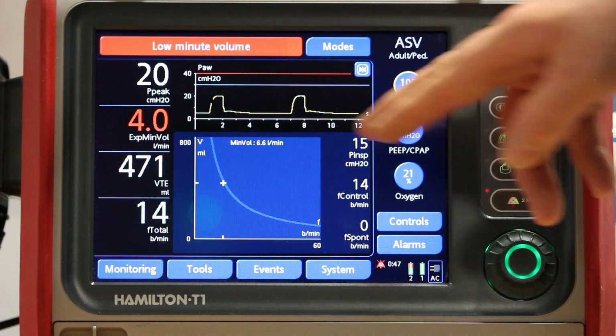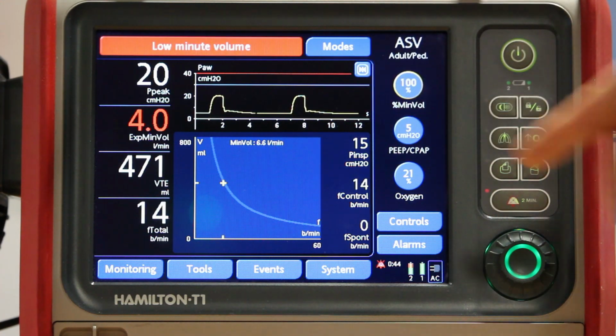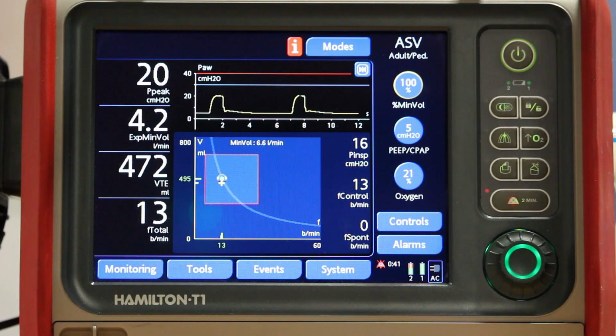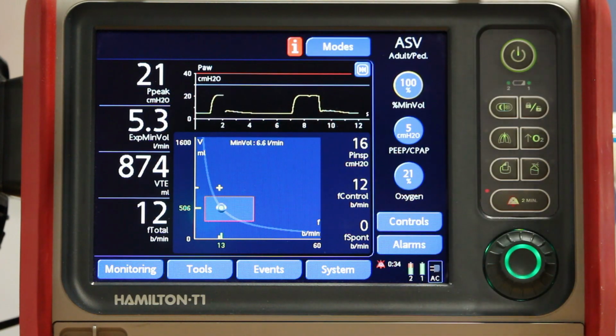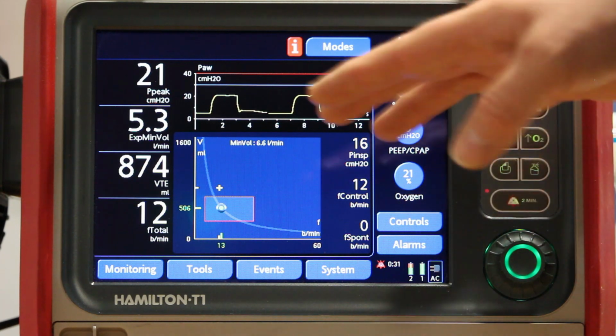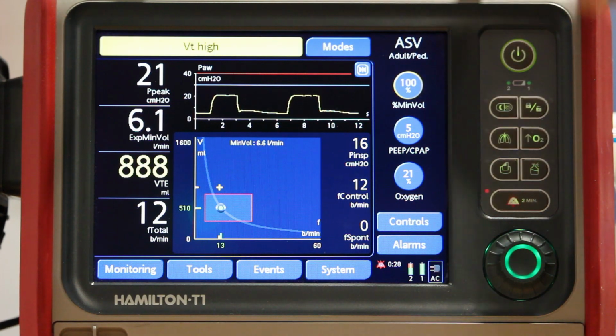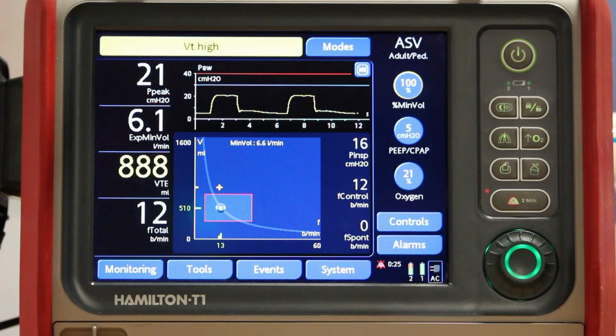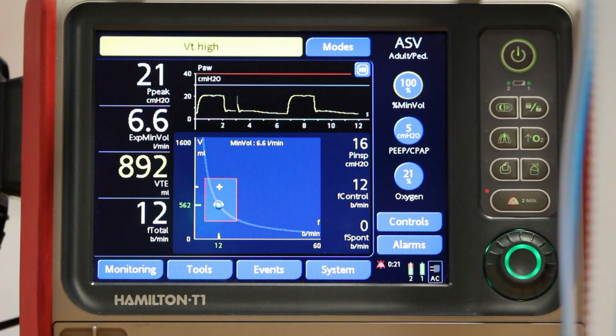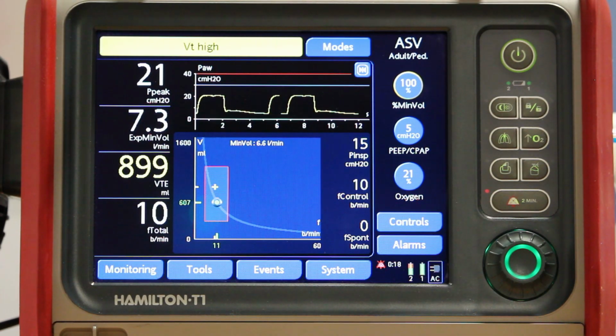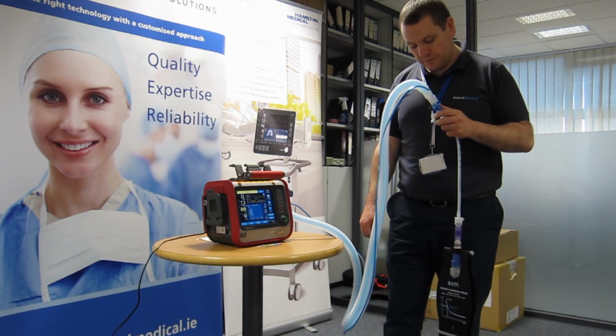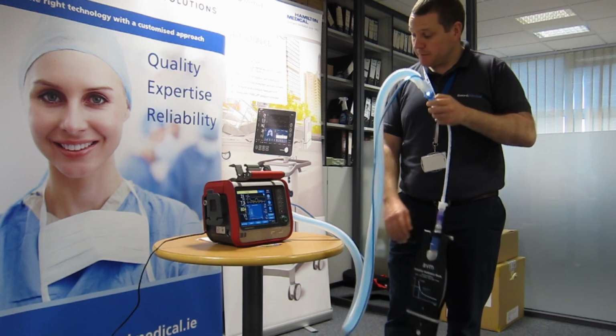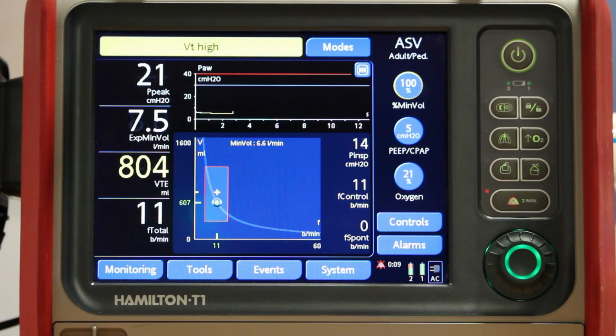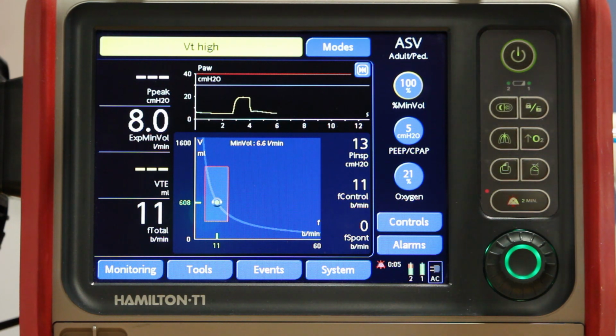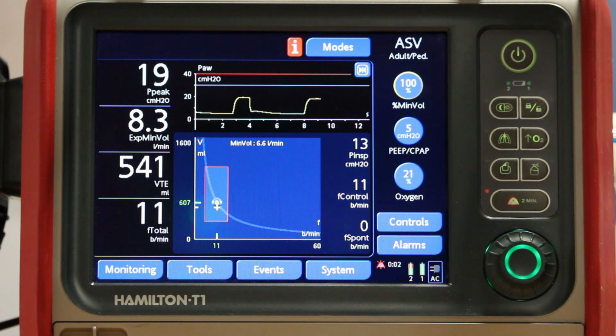So what the vent's going to do is it knows my target minute volume is 6.6 litres a minute, and it's going to use tidal volume and frequency to achieve the target minute volume based on the mechanics of this particular lung. The curve on the graph is all of the combinations of frequency and tidal volume that will achieve the minute volume. The red box is all the safe combinations, and the green dot is the ideal combination of frequency and tidal volume that will achieve the target minute volume. The yellow cross is what's happening with the patient in real time. So, you can see I've done nothing, just put in the height, press start, and the ventilator is starting to ventilate this lung.